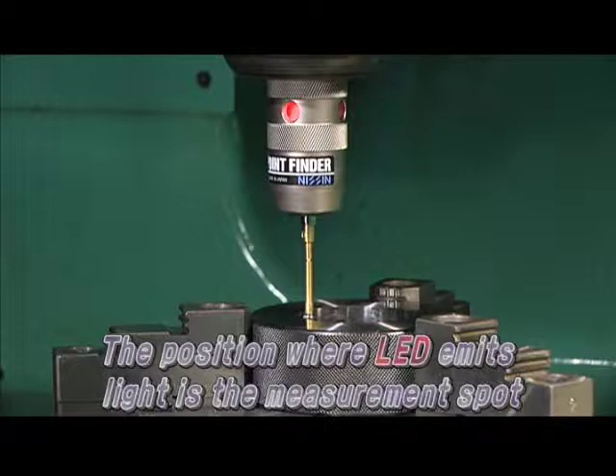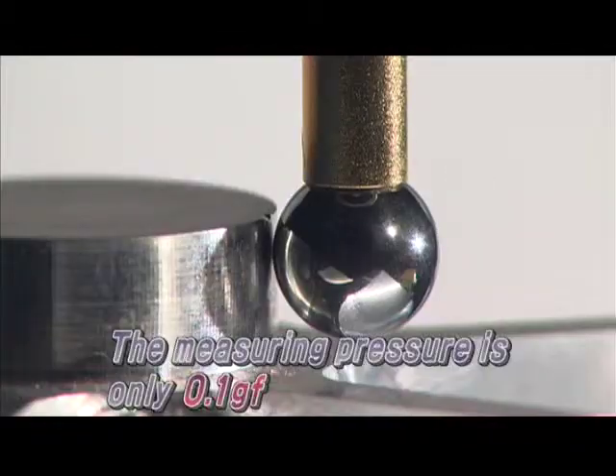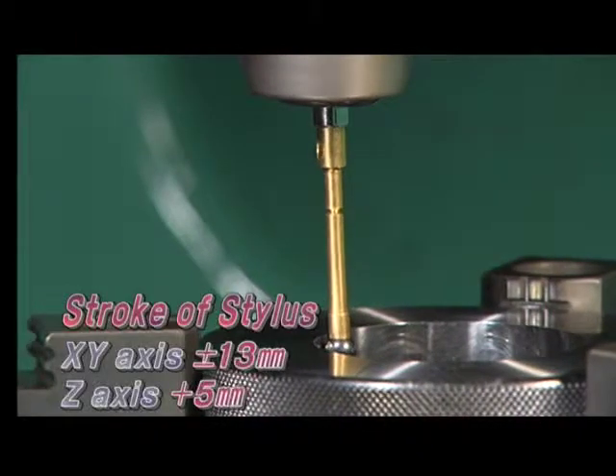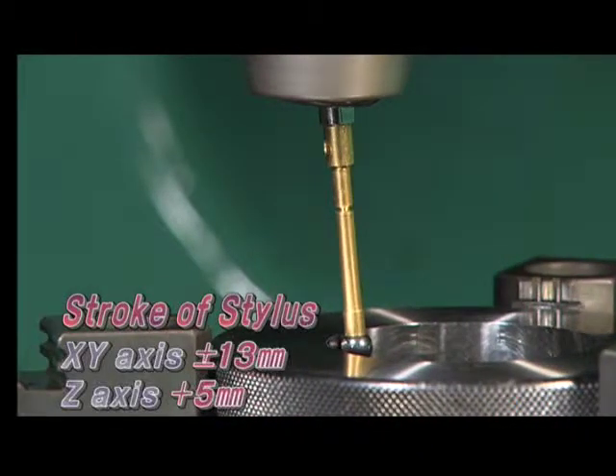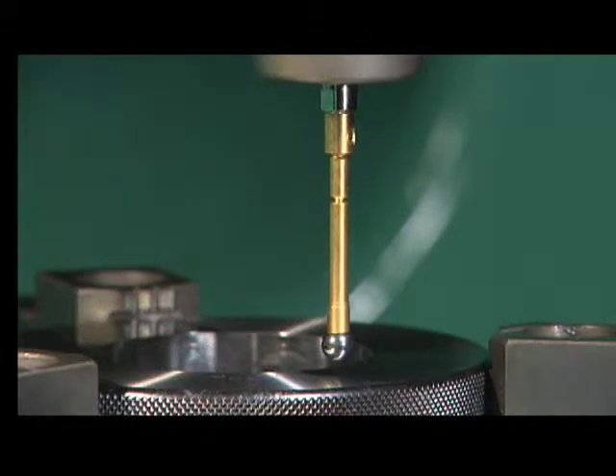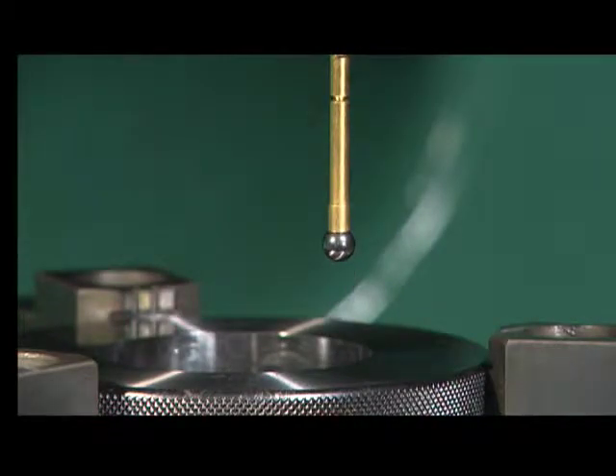the LED is emitted. Because the measuring pressure is only 0.1 gram force, it can measure any thin and delicate workpiece accurately. Its special mechanism in which the stylus swings plus or minus 13 millimeters toward the XY axis and plus 5 millimeters toward the Z axis prevents breakage, and remote control is safe.